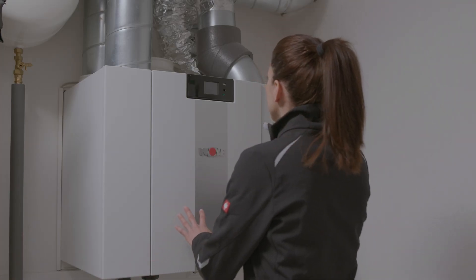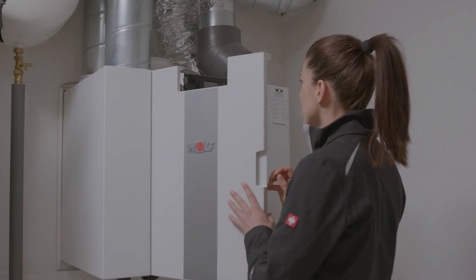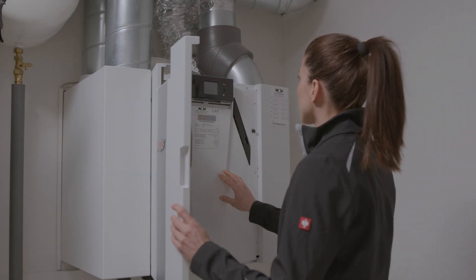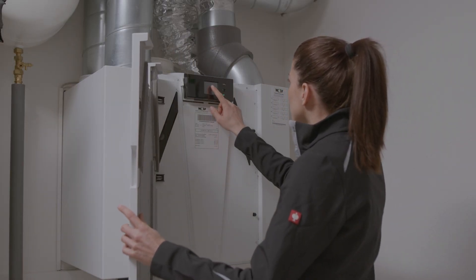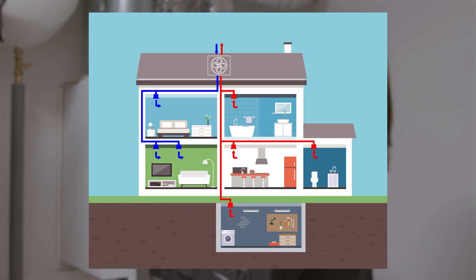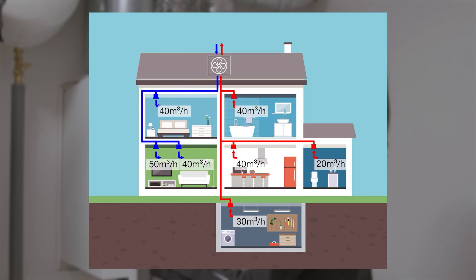A nominal output with total volume flow is defined for a ventilation system. The ventilation plan shows how this is distributed to the supply and exhaust air outlets in the individual rooms. During commissioning, the outlets are set to the target volume flows.